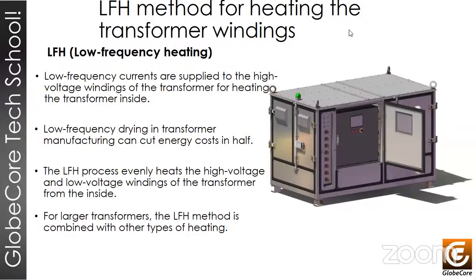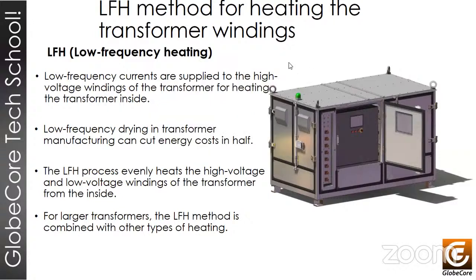In our practical experience, the application of this drying method in combination with other traditional methods of drying the insulation delivers the best possible option as a final product. The equipment with direct electric heating through low-frequency currents is designed for fully automated manufacturing of transformers of various sizes and types, in medium and large batches. High flexibility in loading the batches of transformers is unique and essential, especially in the field of distribution transformers.